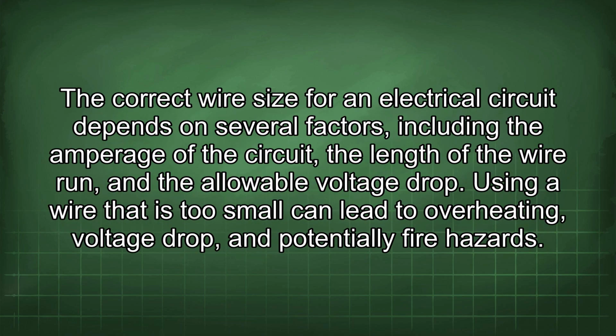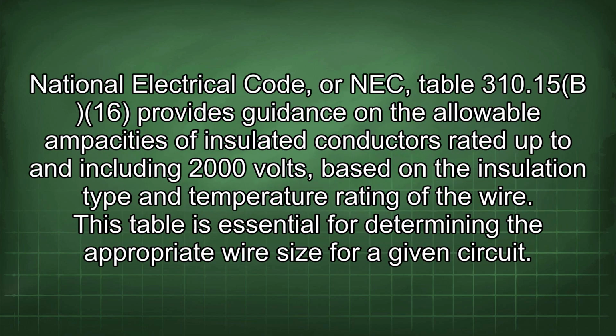The correct wire size for an electrical circuit depends on several factors, including the amperage of the circuit, the length of the wire run, and the allowable voltage drop. Using a wire that is too small can lead to overheating, voltage drop, and potentially fire hazards. National Electrical Code, or NEC, Table 310.15(B)(16) provides guidance on the allowable ampacities of insulated conductors rated up to and including 2000 volts, based on the insulation type and temperature rating of the wire. This table is essential for determining the appropriate wire size for a given circuit.